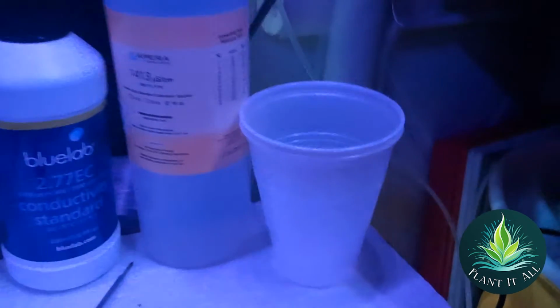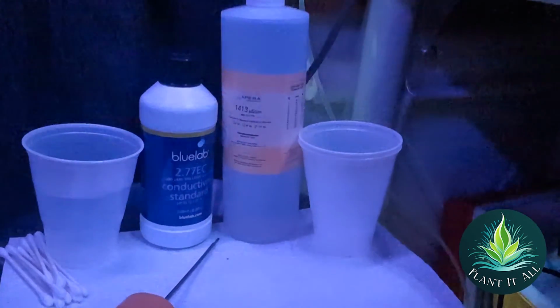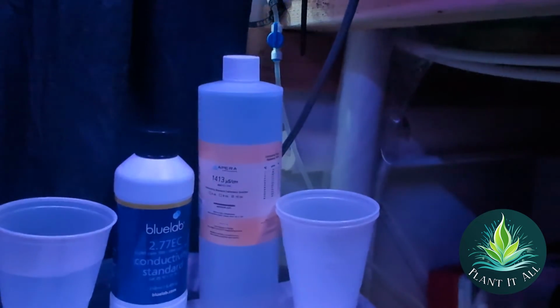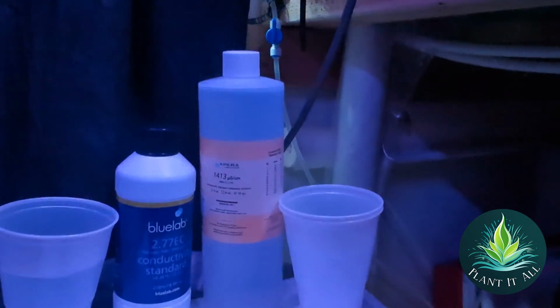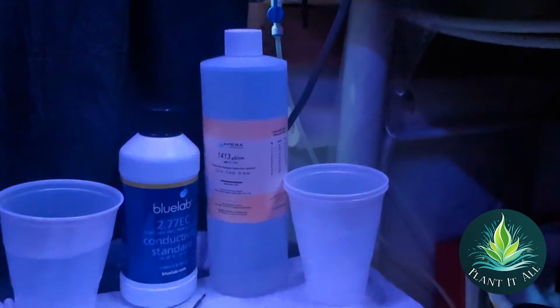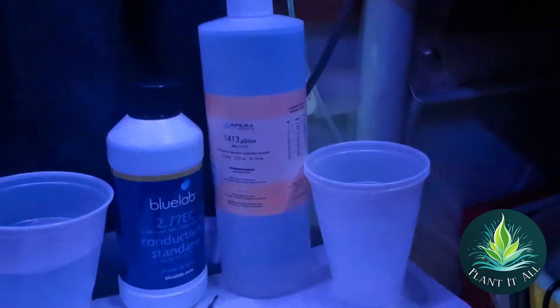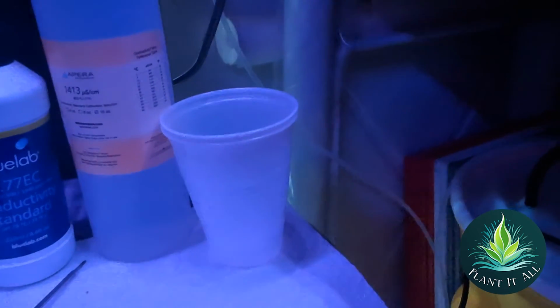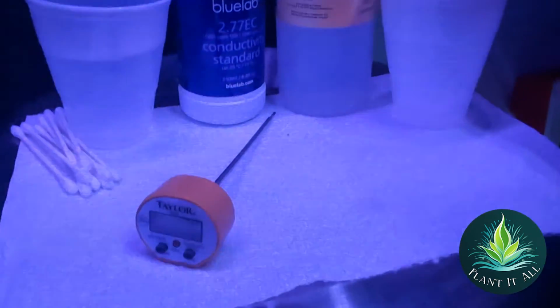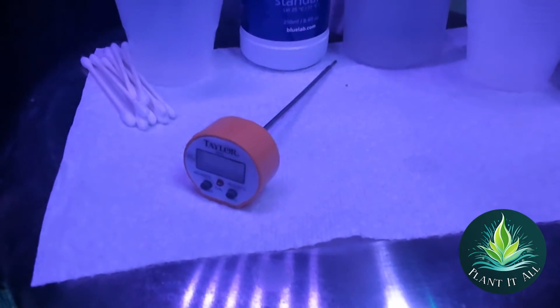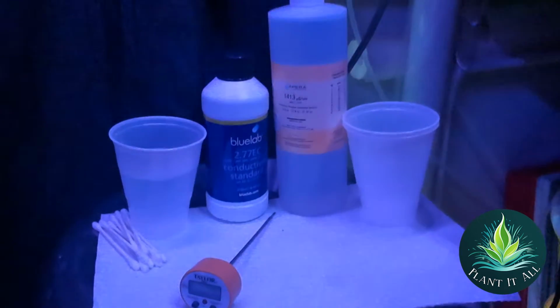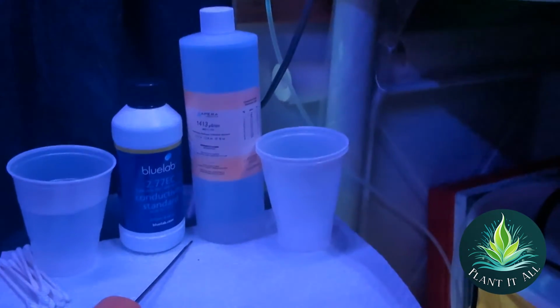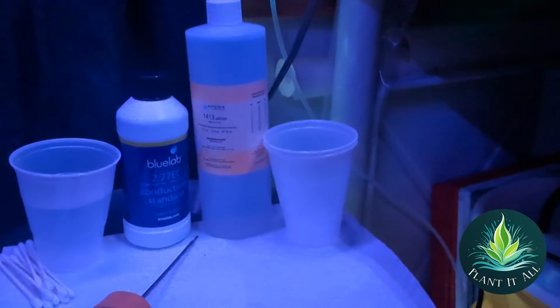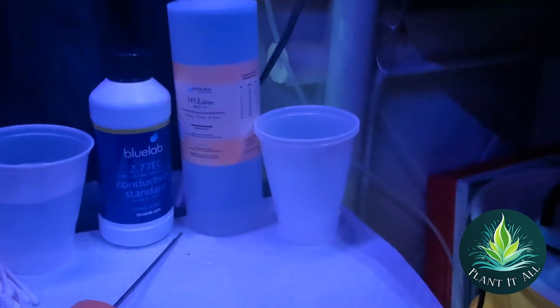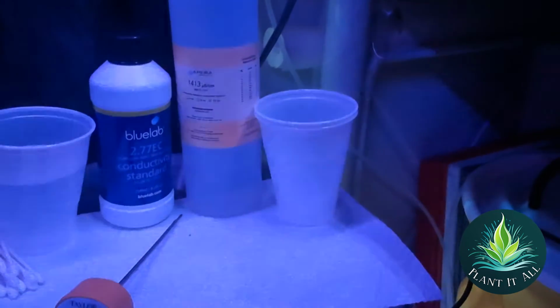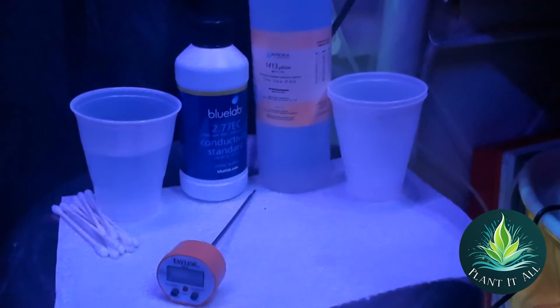Now, one thing that's important to note here, when your bottles themselves are right around 77 degrees, they're going to maintain their temperature fairly well, especially when they're full. More mass takes longer to change temperature. So my recommendation is get these all set, then pour each one in turn when you're ready to use it into the cup, and then confirm its temperature. Now, if your temperature has gone down below 77 degrees, you can certainly put the cup gently back into your water bath, warm it up a little bit, get back to 77, or if you're over, that smaller amount of liquid in that cup is going to cool faster. All right, so let's take a look at the Growee app.